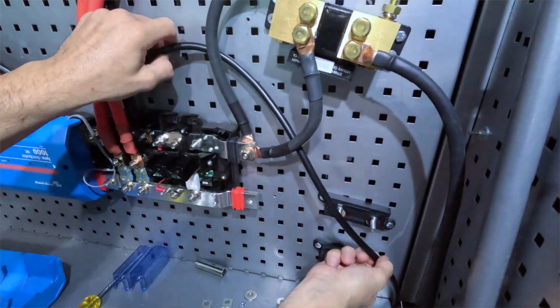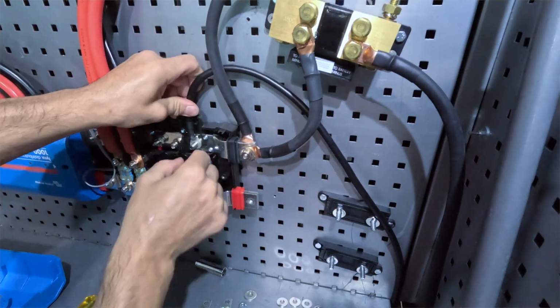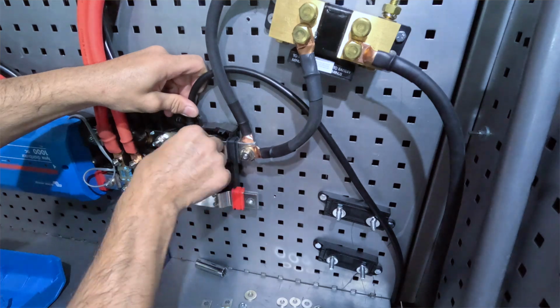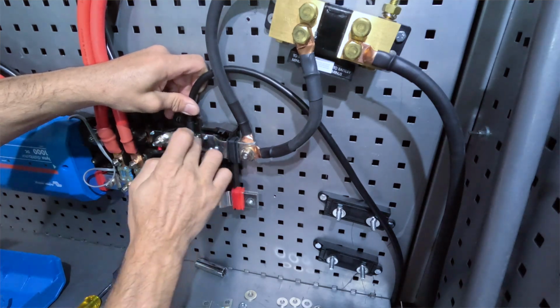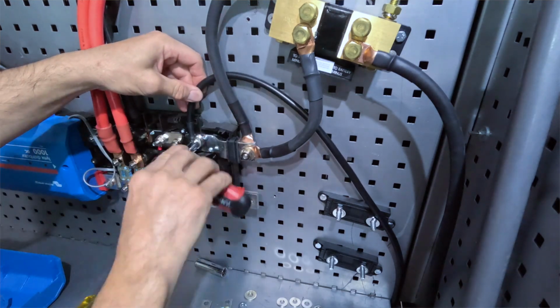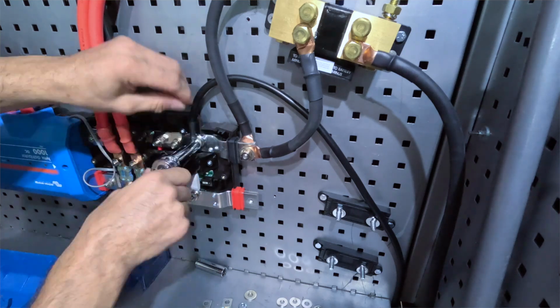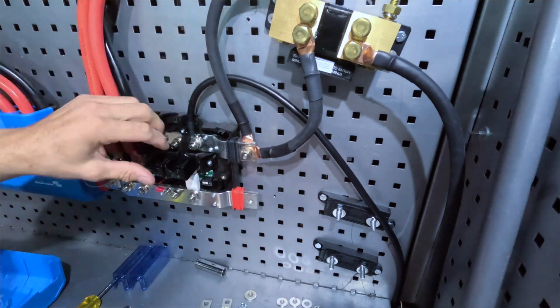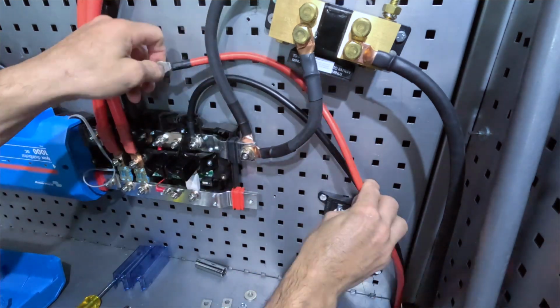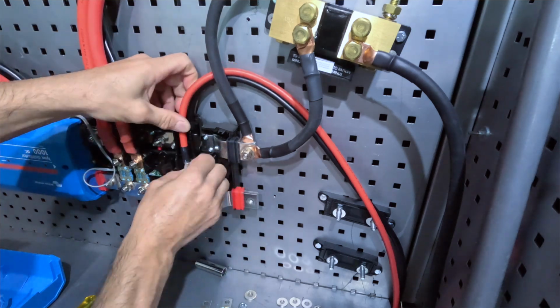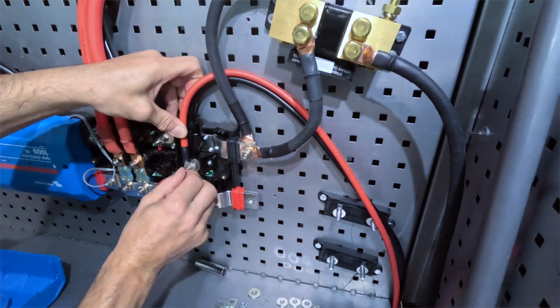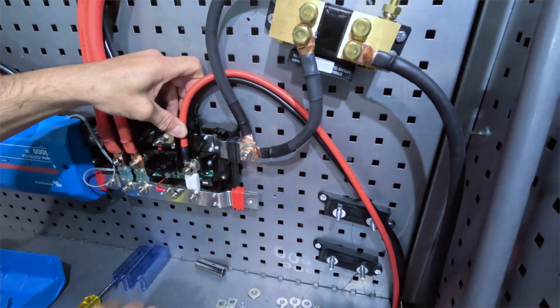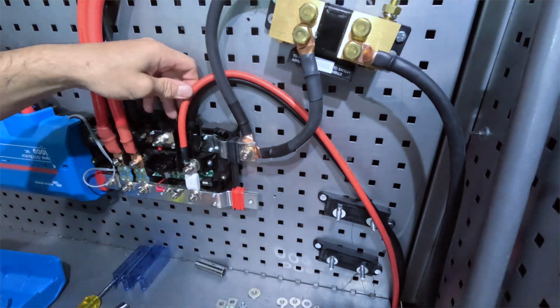As the last connection, we are connecting the EG4 3000 watt inverter with a 125 amp fuse. Just for reference, we connected the MPPT with two 125 amp fuses, and each inverter with two 200 amp rated fast-acting fuses. And we are going to mount two fuse plugs for the batteries as well.